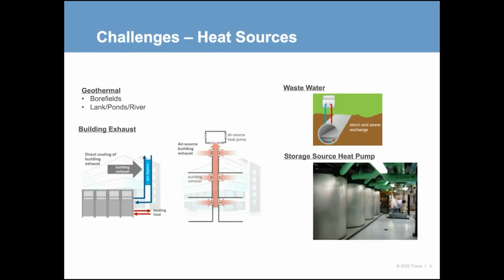The next thing, I said this before, is air to water heat pumps are getting looked at for a lot of electrified jobs, specifically on the hydronic side. But if you think about a big building in a big urban setting, you probably have a boiler stuck in your basement, right? That's what you're doing all your heating from. If you want to replace that boiler with air source equipment, that's equipment that needs ambient air, do you have enough space to fit all of that equipment? And if you don't, the question becomes, where else are you going to get that heat from? And that's where we see a lot of innovative designs coming right now.